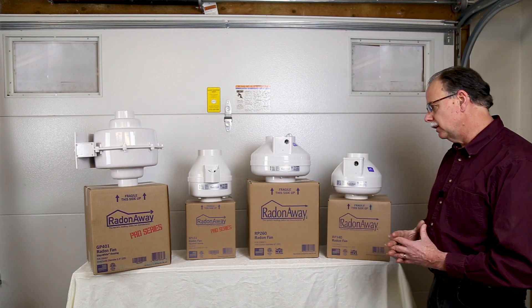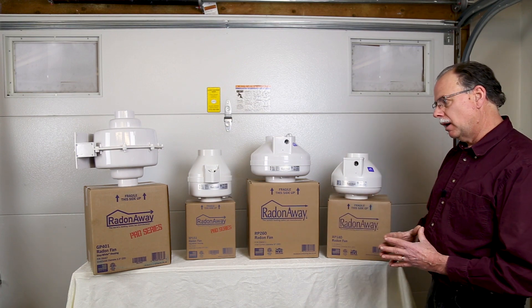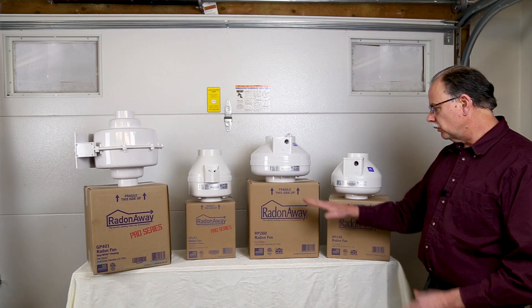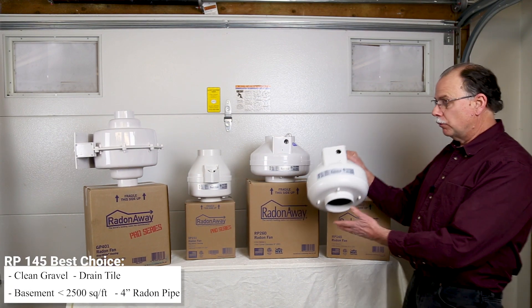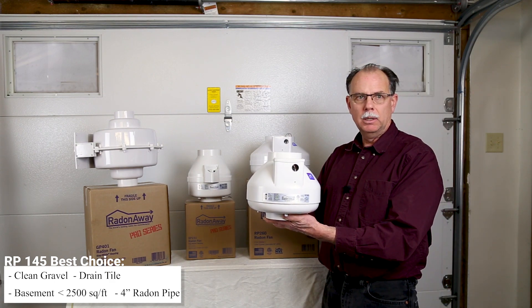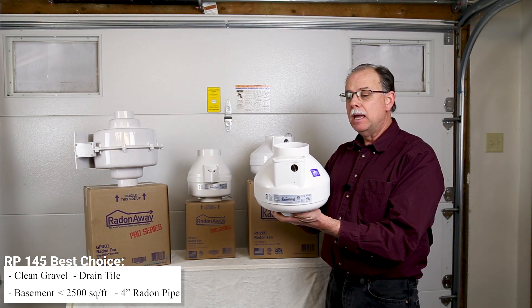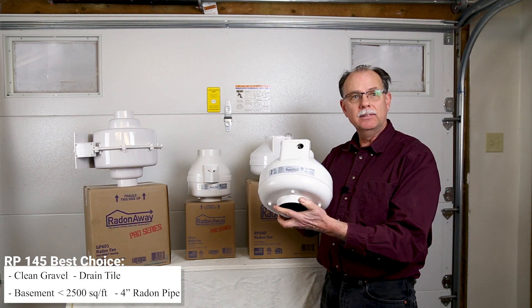Let's take a look at these four fans here that we've installed. This is representative of the three series of radon fans by the company RadonAway. First they have the RP series fans. The RP 145 is probably the most common radon fan installed in the United States today. It's a four inch radon fan, a medium pressure fan, and it's able to move a lot of air — about 170 CFM.